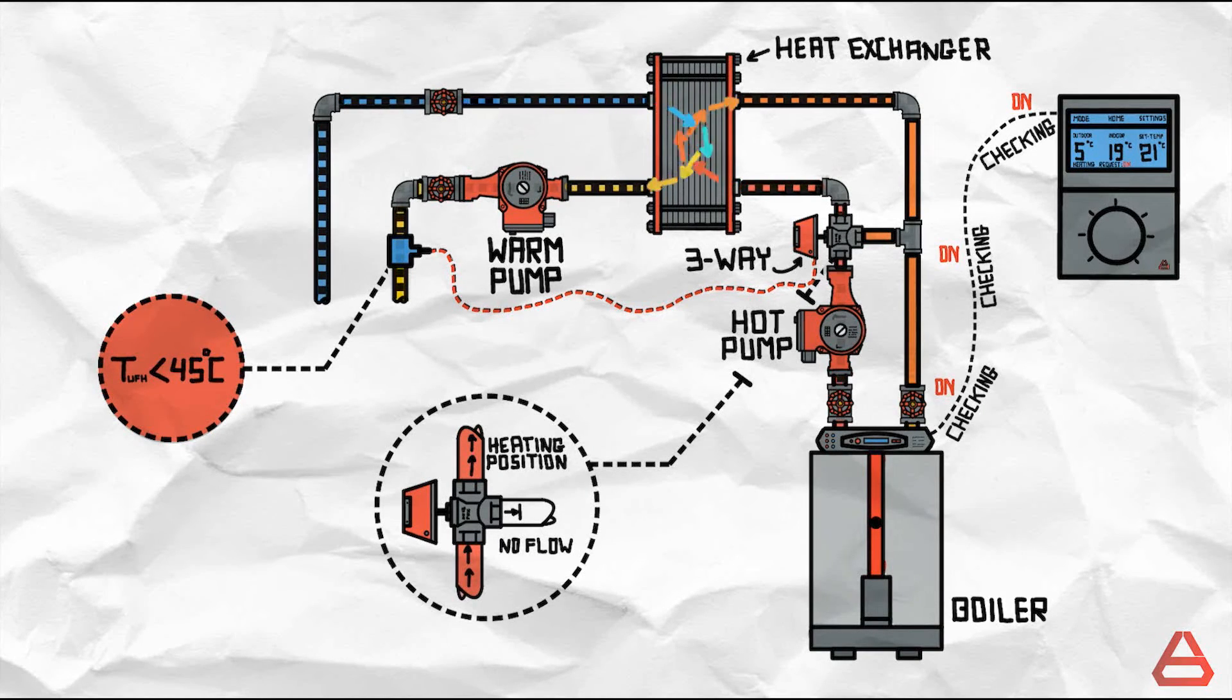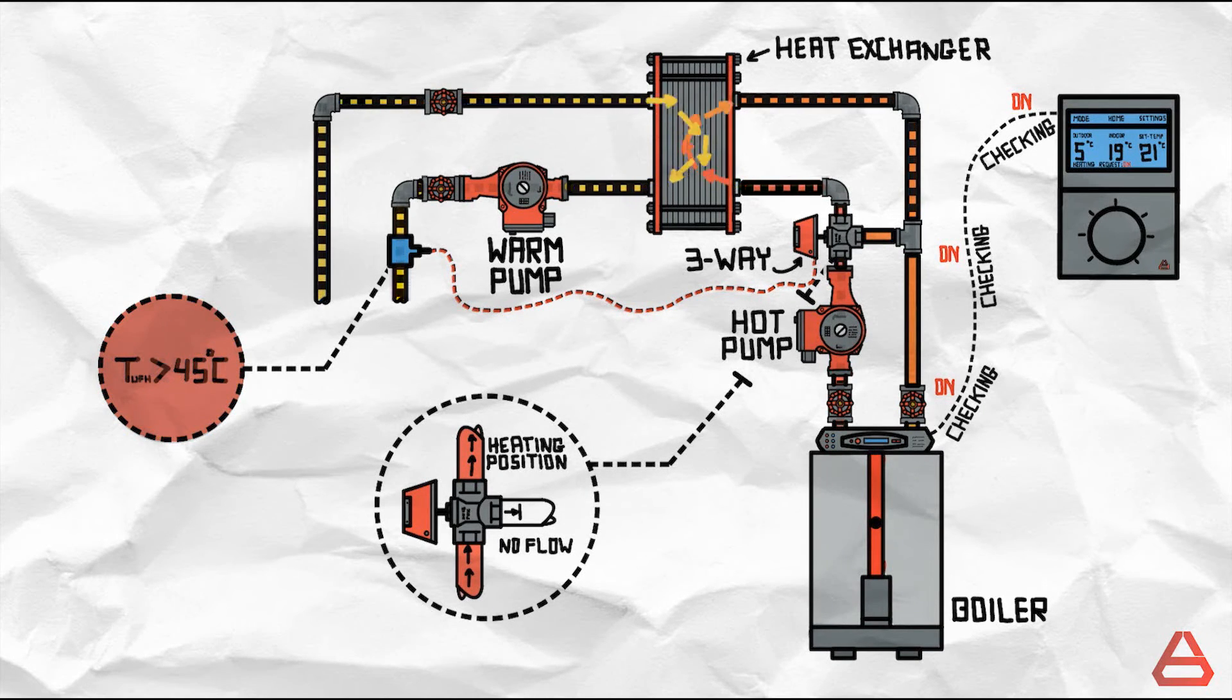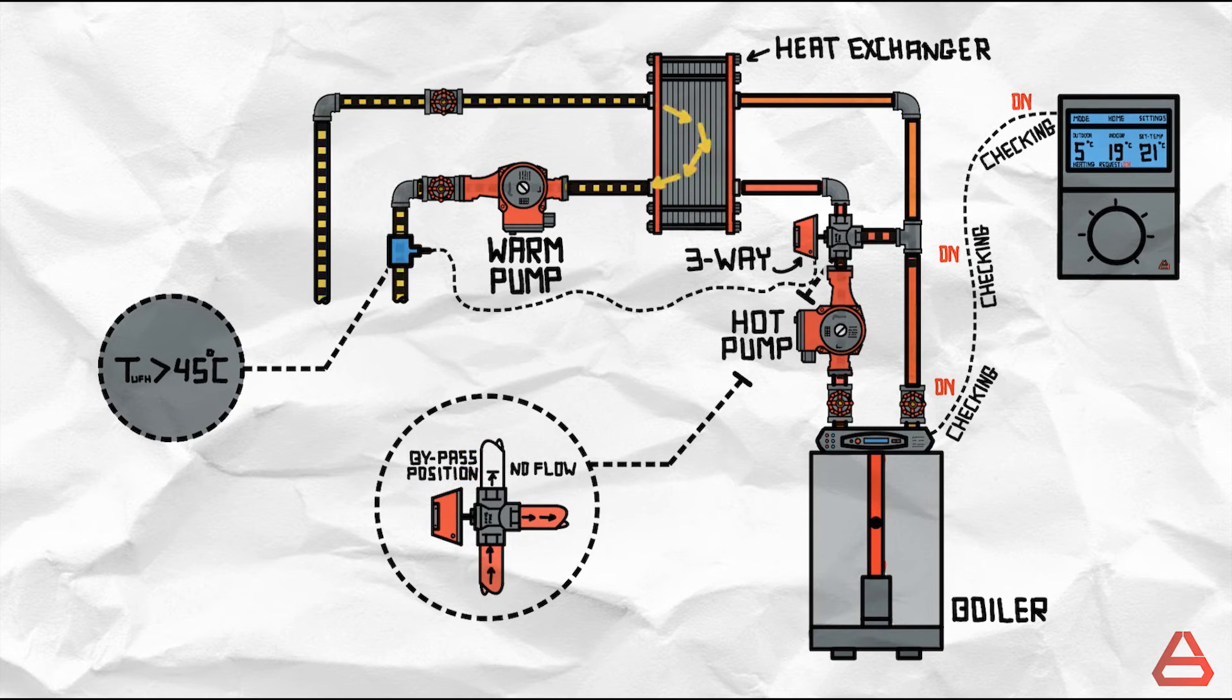After some time the water flowing in the warm circuit has reached a few degrees above 45. The sensor detects this and the three way valve assumes bypass position and redirects the hot water back to the boiler instead of the heat exchanger. The warm circuit temperature increase now stops.